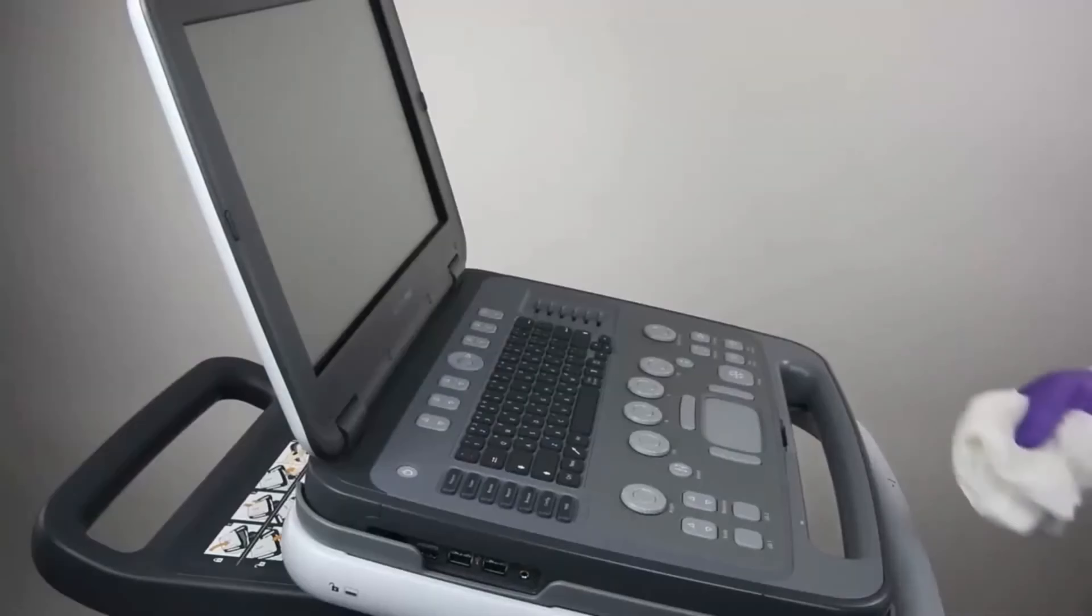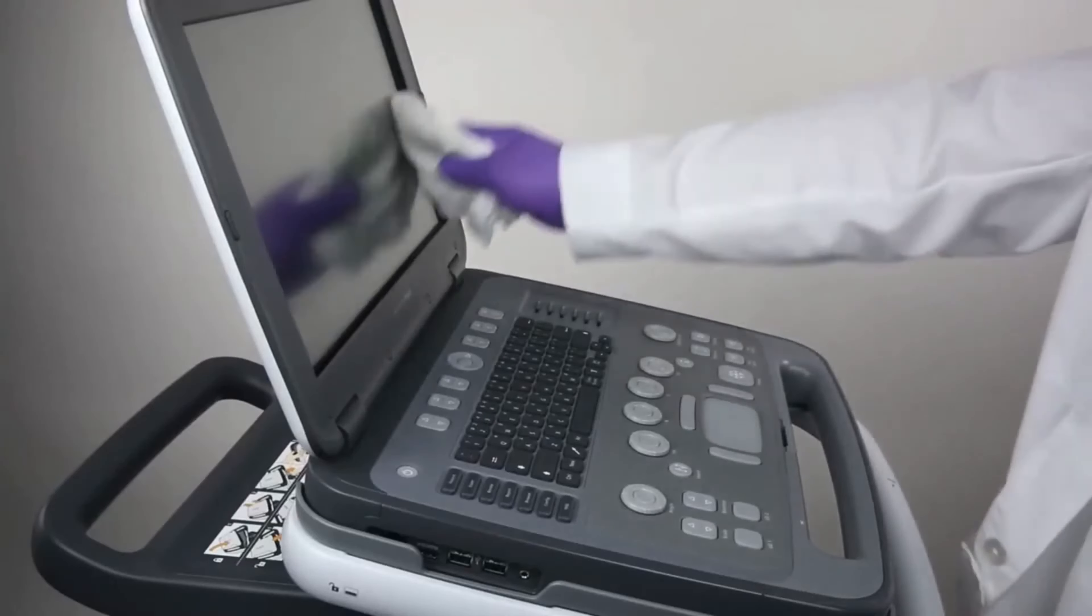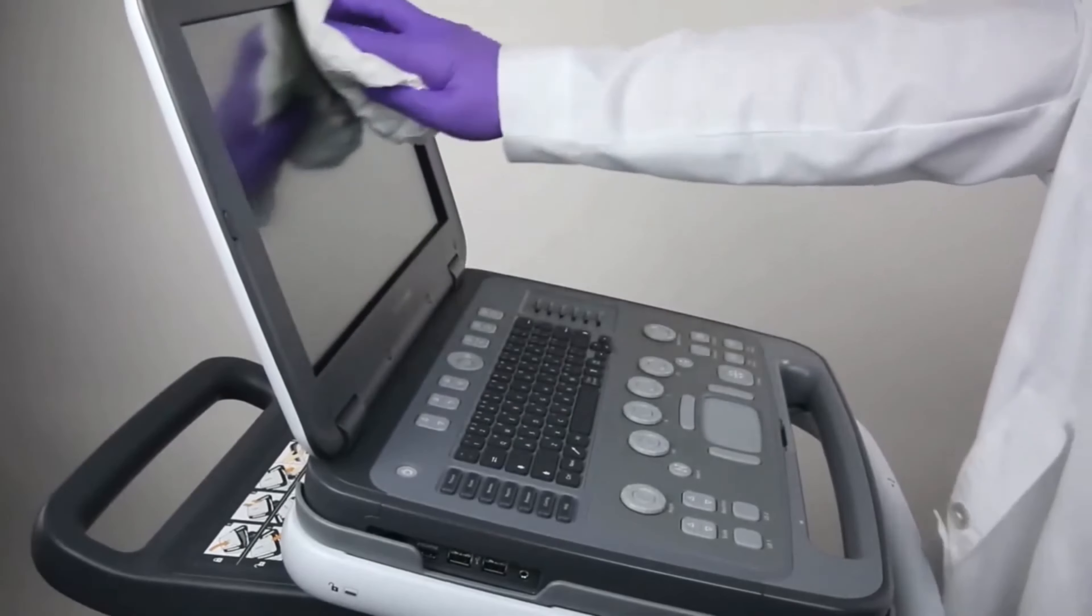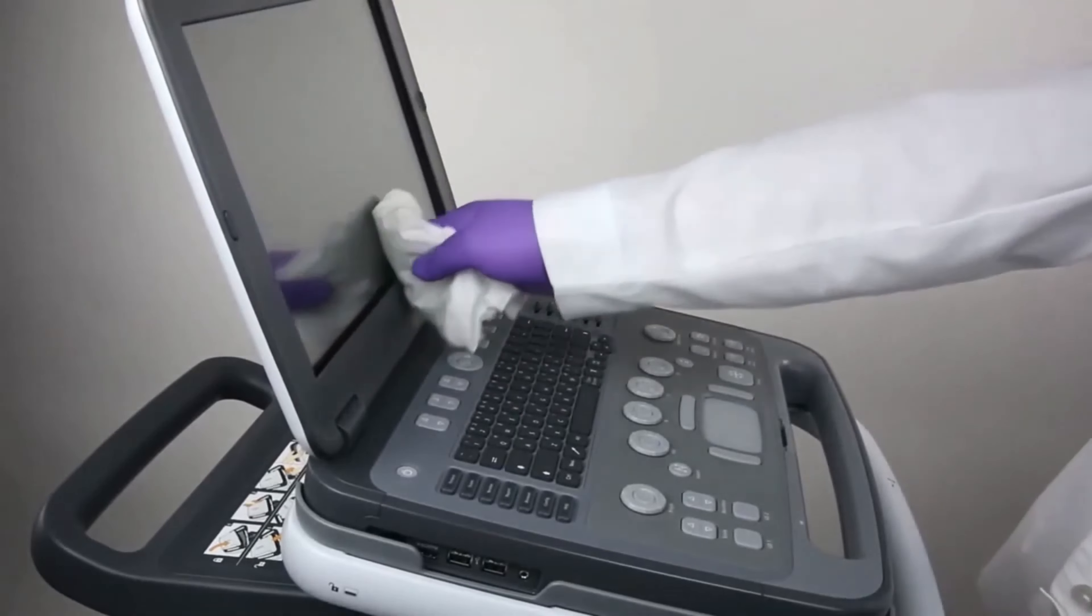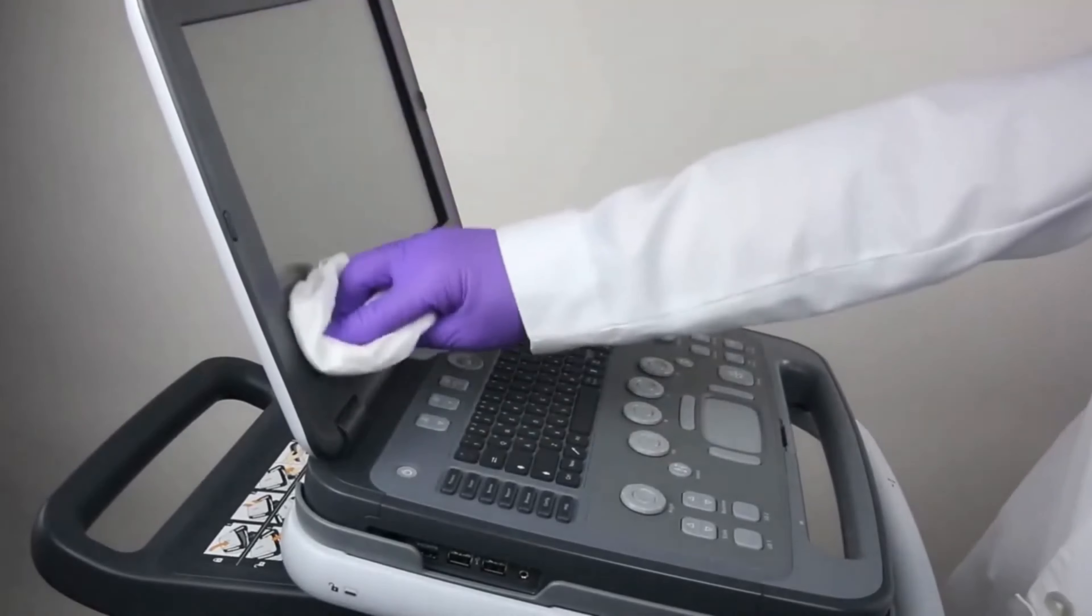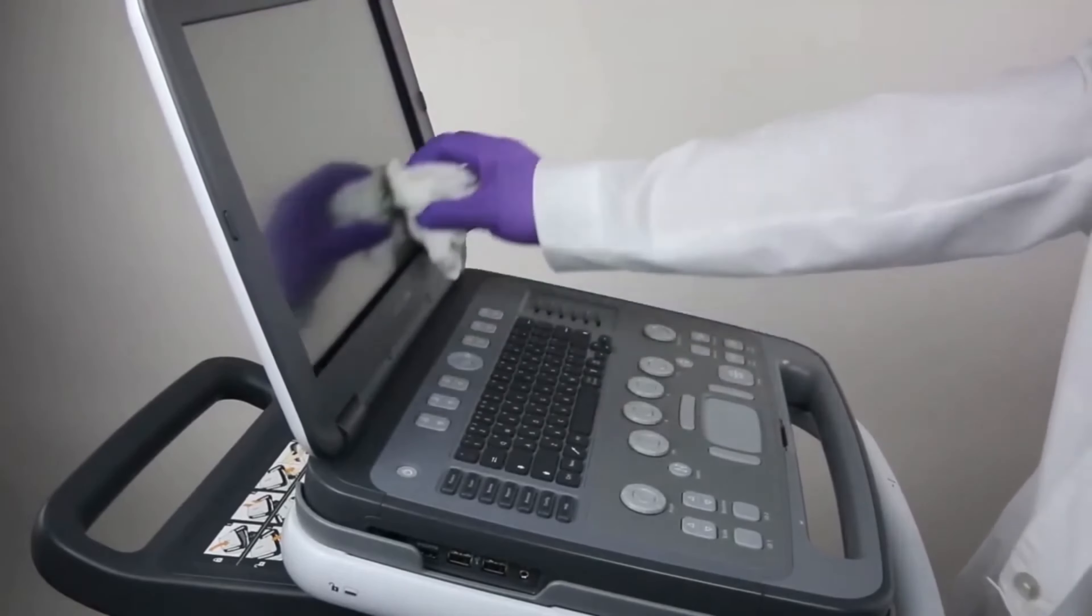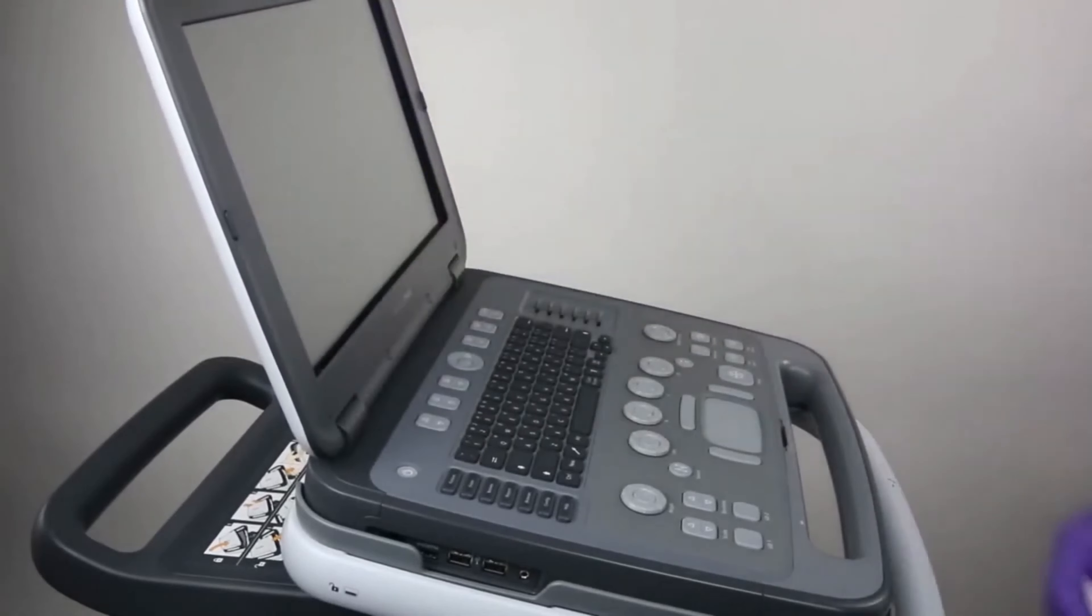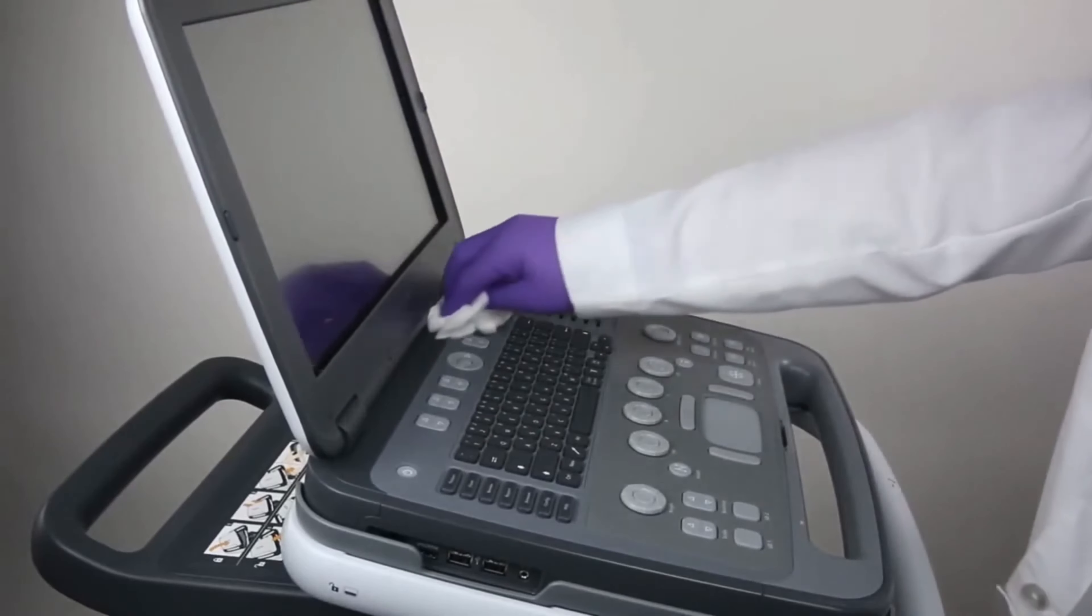Lightly moisten a clean gauze pad or lint-free cloth with mild detergent or an approved disinfectant. When cleaning the touch screen, use only mild detergent or water. Applying disinfectant to the touch screen may damage the surface. For a list of approved cleaning and disinfectant agents, refer to the user manual.